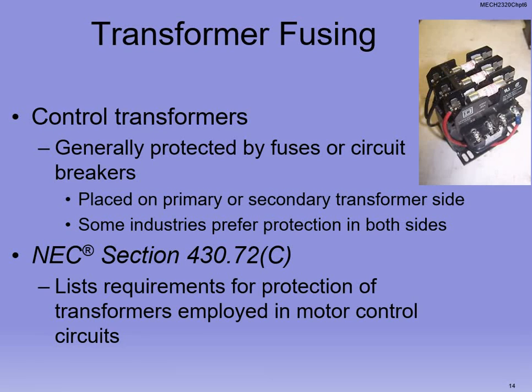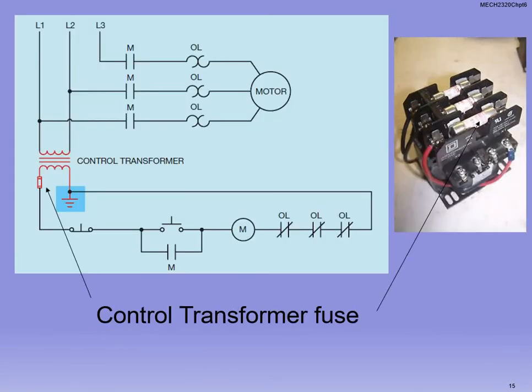side of the transformer. You don't put them on both sides because it's kind of insignificant there, right? Or it's redundant, essentially. But you'll have them on one side. So if you get more into this in industry and things like that, you're going to have to actually look everything up. So the NEC code, which we've mentioned multiple times, if you open up to that specific section, it tells you the requirements for the protection of transformers. And because transformers come in multiple sizes, multiple taps, step up, step down, you're going to have to look at your specific transformer to understand what the specs are and how you need to protect it.